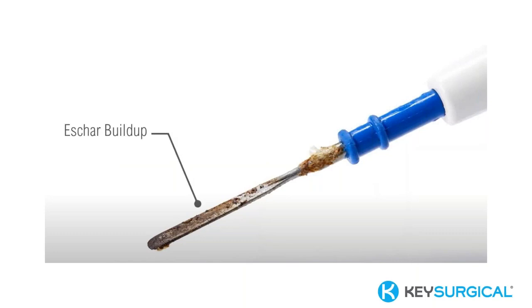In the operating room, this eschar can be dangerous for many reasons. You can't see your surgical site as well, right? It's an insulator, which can impede the electrical current going through that instrument. Because it's so hard and challenging to remove, it takes away time. It causes frustration, of course. And relevant to our discussion today, sometimes other things that should not be used to remove eschar, such as the back of a knife handle, are used. When we use these tools, it's so close to where the insulation is that the insulation can actually be damaged where you're scraping and peeling it off.